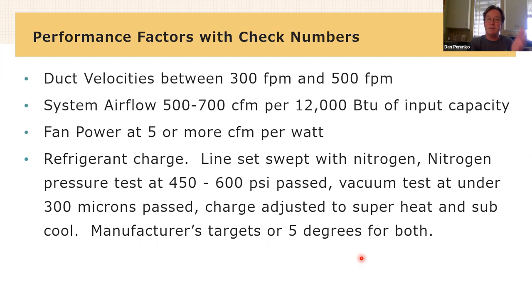When you're sizing ducts, you would use these metrics: 300 to 500 feet per minute air speed of the airflow in each duct. So you need to know how much air is going through each duct, which means you need to know how much air goes to each room. Total system airflow of 500 to 700 CFM per ton of capacity. Fan power should be less than... you should get more than 5 CFM per watt of power, or else you have too much resistance in your system.